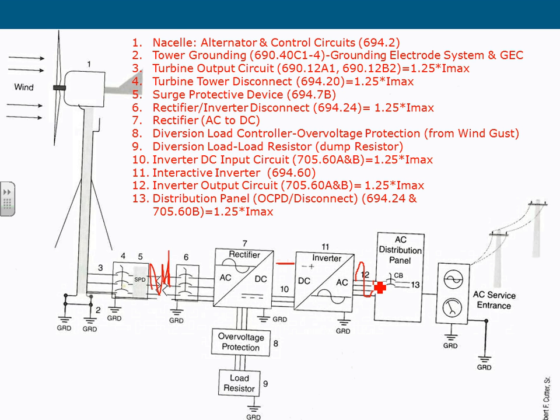You have the over voltage protection and diversion load. These two are part of controlling your gust. You get a big gust over here, big voltage, big current coming out of it. Instead of dumping it in here, you can divert it as part of your control of the turbine. You can dump it through a bunch of resistors and burn the energy. So that's your number 8, the so-called diversion load controller and over voltage protection from gust. I just added here from gust. And the resistor sees a higher voltage, higher amps than it can handle, so it diverts it directly and burns it through these resistors.